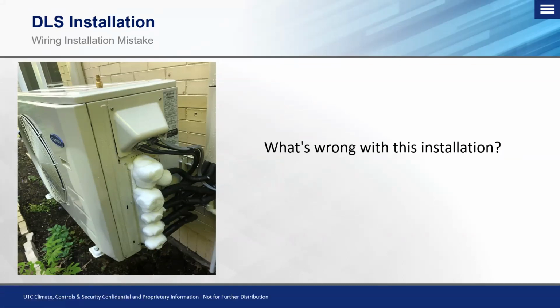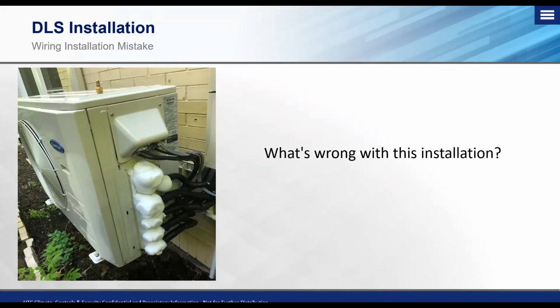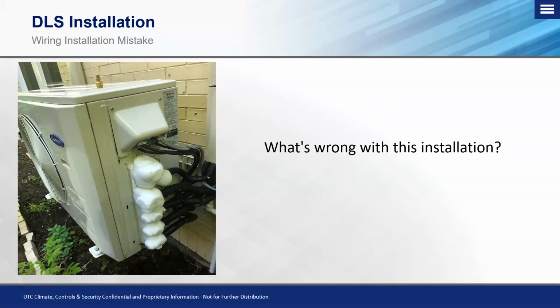So you go, okay, well, what causes this? Remember we were talking about the multi-zone situations where you can crisscross wires? This is a syndrome of that. So what happens is when you cross, let's just say zone A and zone B, and zone B and zone A are now crisscrossed with wiring, zone A calls, but zone B is getting refrigerant. And that fan's not running. So the fan's not running, it's getting mixed phase refrigerant, and it's not boiling off properly into a suction gas because we're not passing air across the coil.